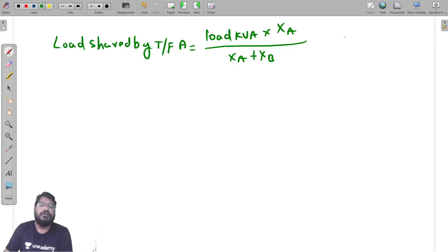Now substitute to find the load shared by each transformer. Load shared by transformer A is equal to load kVA into XA divided by XA plus XB. So load kVA is 1000, multiplied by, with XA as 0.02 and XB as 0.08.